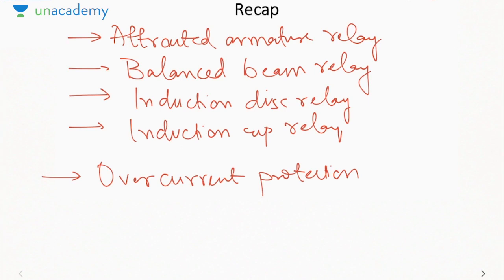Then IDMT, in which it showed inverse characteristics at low values of fault current and definite characteristics at high values. Then very inverse, which was more inverse than the inverse type and had better selectivity. Then extremely inverse, which had the best selectivity, and hence it can distinguish between the magnetizing inrush current and your fault current. Then we saw certain terms associated like plug setting multiplier, relay setting, relay operating current. These sort of terms we saw in conjunction with the overcurrent protection.